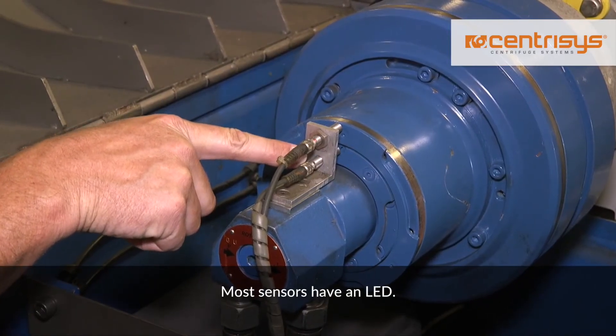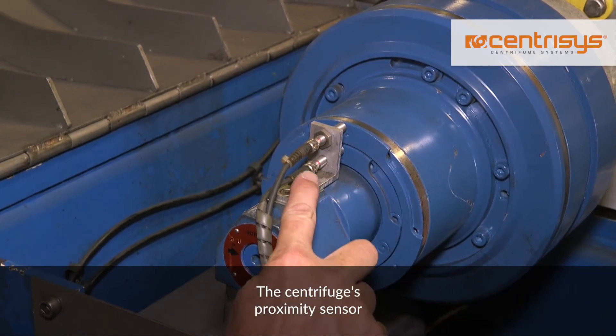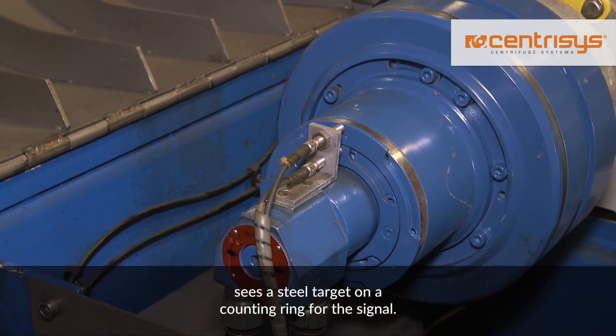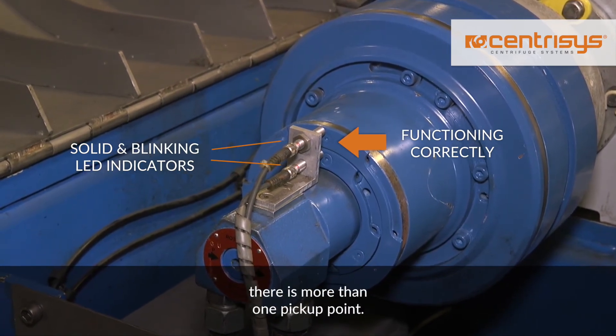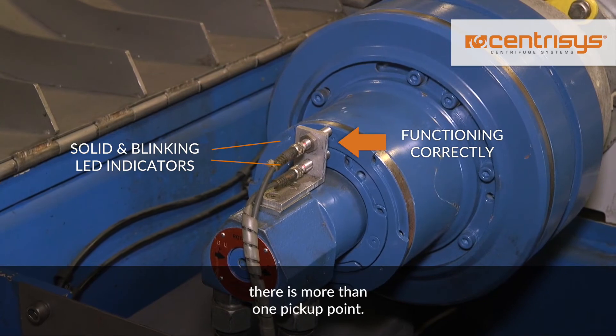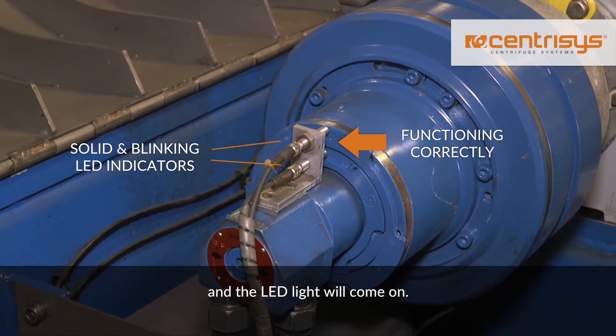Most sensors have an LED. This lights up when the signal is detected. The centrifuge proximity sensor sees a steel target on a counting ring for the signal. To guarantee the accuracy of the sensor, there is more than one pick-up point. The pick-up point rotates by the speed sensor and the LED light will come on.